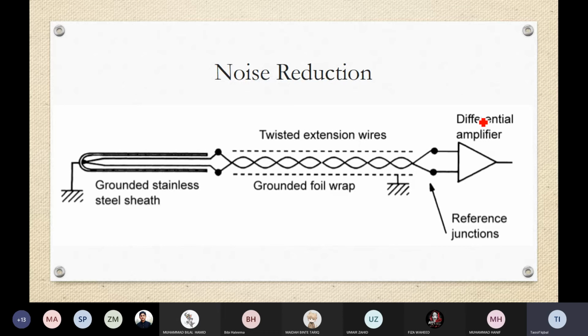As we said earlier, over a long distance the voltage drop of the wires can affect the readings, and since the voltage is already in millivolts and microvolts, to increase the sensitivity of the measurement we can use a differential amplifier having a certain gain. Okay, we will be using a differential amplifier with a high gain so that we can increase the sensitivity of the measurement.